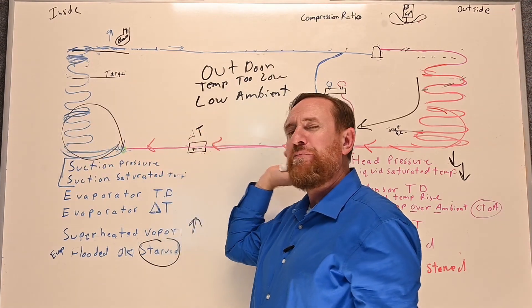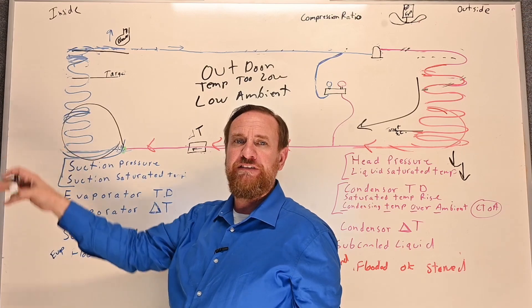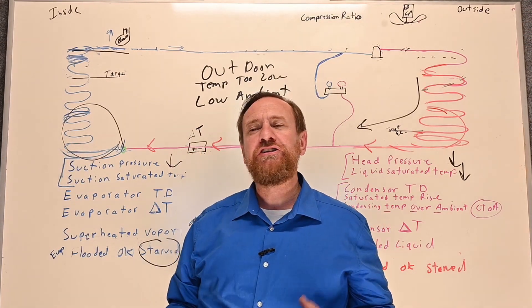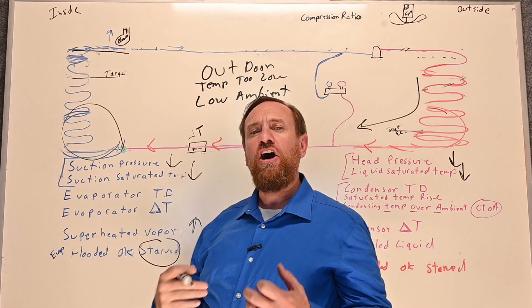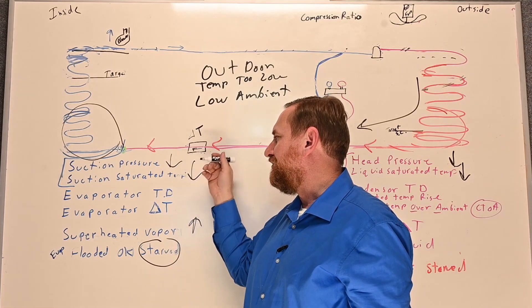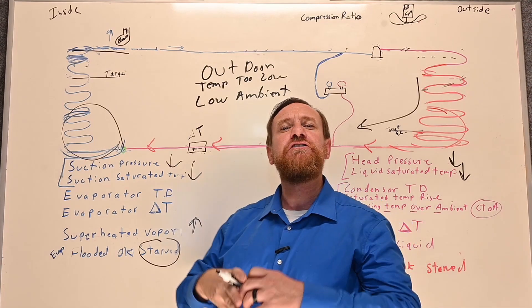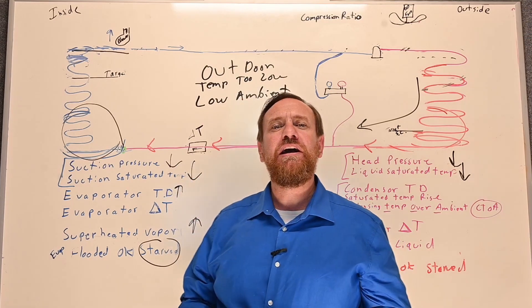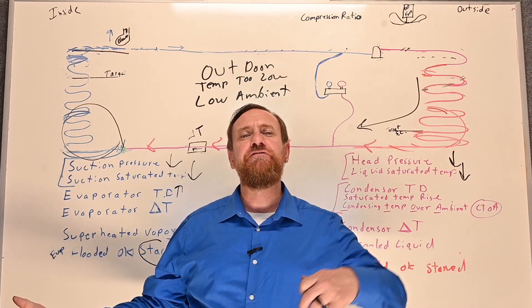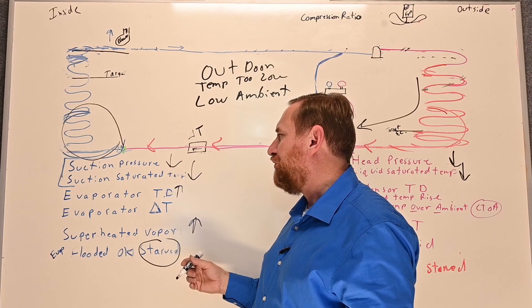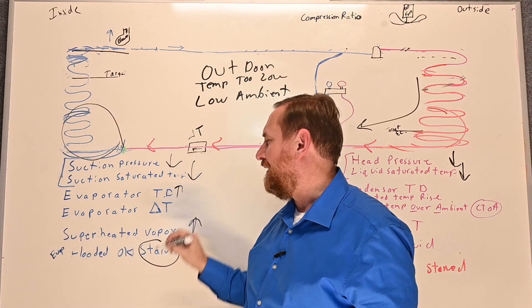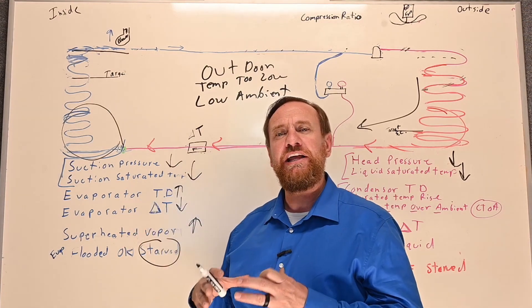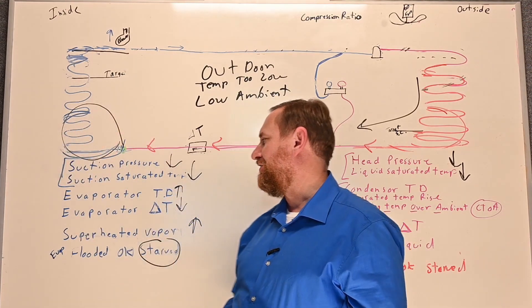Now, because I have less pressure feeding my evaporator coil and less refrigerant in my evaporator coil, I end up with my suction pressure dropping. And we know when our suction pressure drops, our suction saturated temperature also drops as well. And because our suction saturated temperature drops, we're much farther apart from the air temperature. So our evaporator TD ends up going up. There's a bigger temperature difference between the refrigerant and the air. Ultimately, because I have less refrigerant boiling, changing state from liquid vapor, my delta T temperature will end up going down. It comes closer together. I'm overall absorbing less BTUs of heat energy.